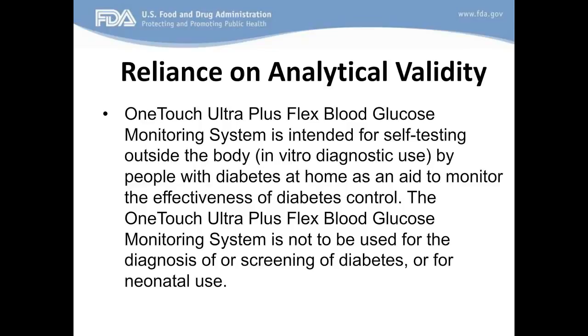This has further clarification, that is that the meter is not to be used in diagnosis or screening of diabetes or for neonatal use. The reason that those warnings are there is because even though there is plenty of data that glucose measurements can be used for such things as diagnosis or screening for diabetes or for neonatal use, the meter that is in hand has not been evaluated at the appropriate places to be able to determine whether it can safely be used for diagnosis or screening of diabetes or neonatal use. For diagnosis or screening, you need a very accurate and precise meter. Handheld glucose meters typically are not sensitive enough and will not give values that allow you to diagnose diabetes.